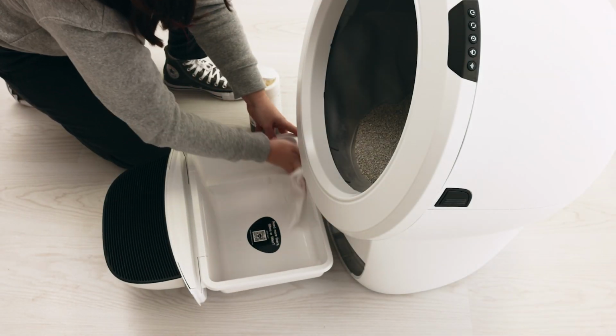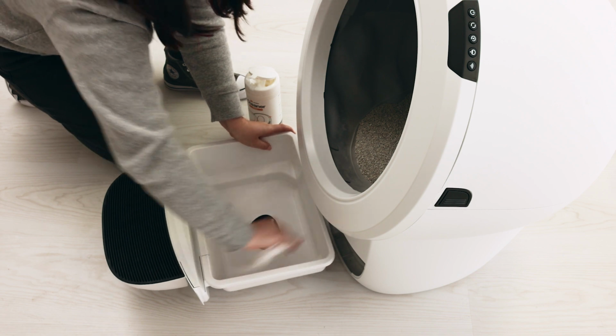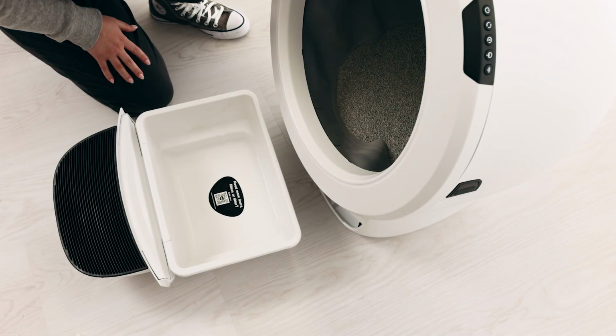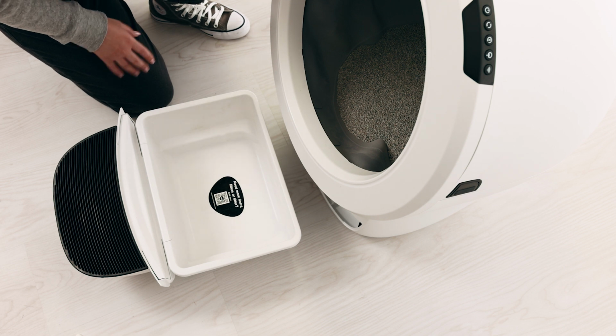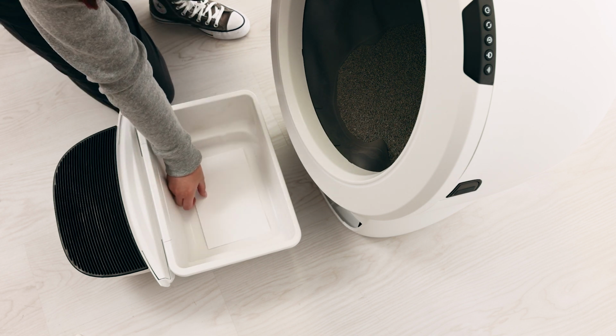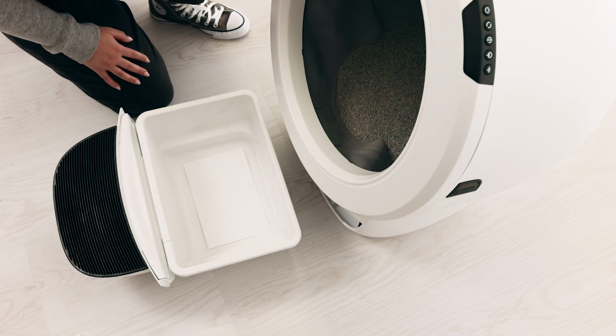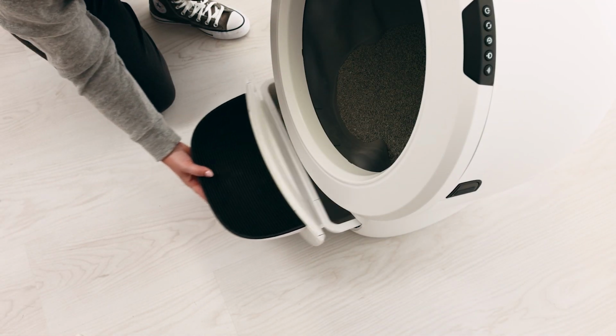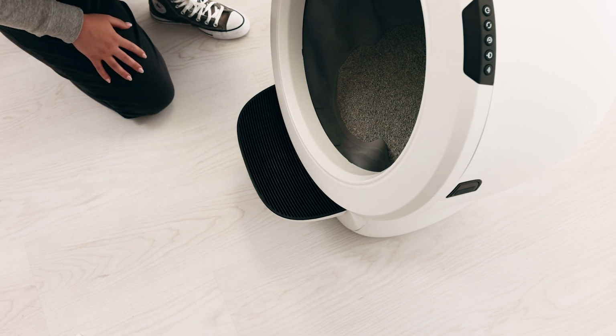Remove the waste drawer liner and wipe the drawer clean of debris. Add a piece of plain white paper to the bottom of the drawer, for example, a half sheet of printer paper. The purpose of the white paper is to provide a reflective surface for the DFI lasers. Make sure the paper is plain white and does not have a pattern. Also make sure that it will lay flat on the bottom of the drawer. Insert the waste drawer again. Do not add a waste drawer liner yet.